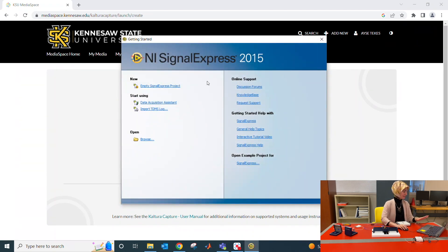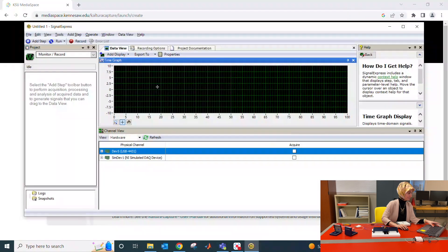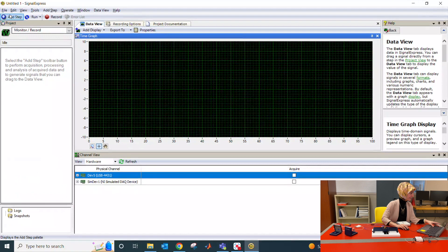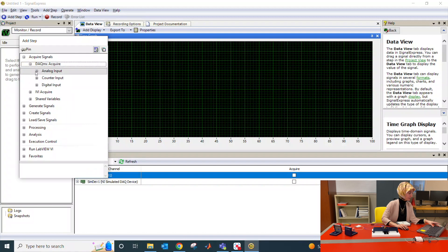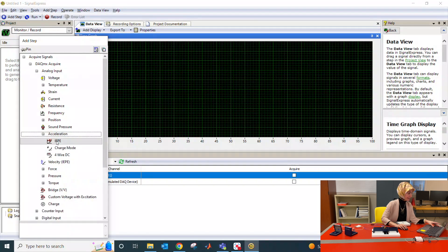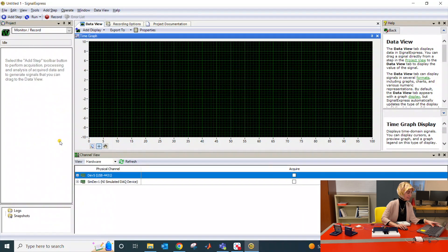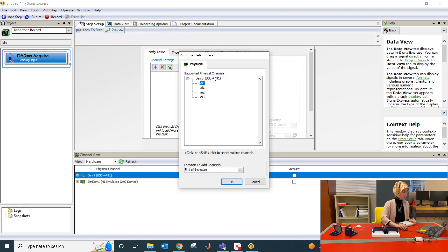Once you see the NI Signal Express app, please click on 'Empty Signal Express Project.' Then expand the menu and click on 'Add Step.' Select 'Acquire Signals' from the data acquisition card — it's an analog input. We are reading acceleration, so please click on acceleration and then select IEPE. Remember, I connected the triaxial accelerometer to channel zero, so I will only click on channel zero.